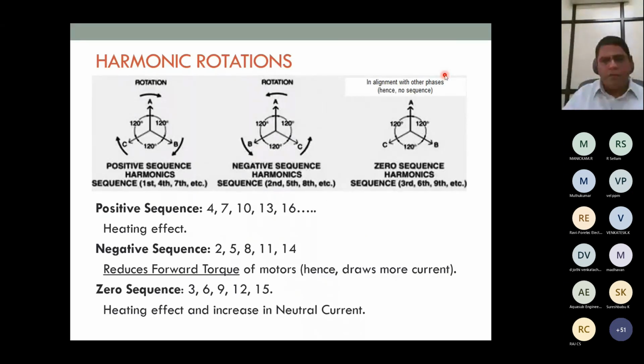Another one is rotation, harmonic rotation. There are three sequences. One is called the positive sequence, second is called the negative sequence, and the other one is called the zero sequence. So positive sequence is 4, 7, 10, 13, 16, like that. Positive sequence harmonics mean it is in line with the sequence of our supply frequency.